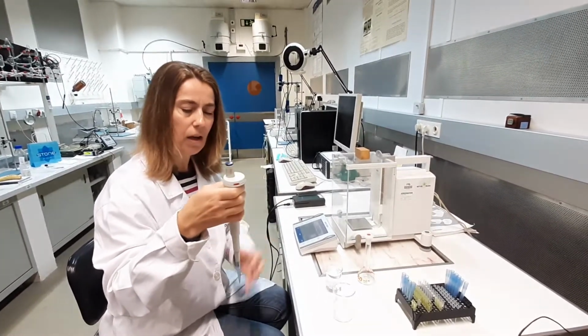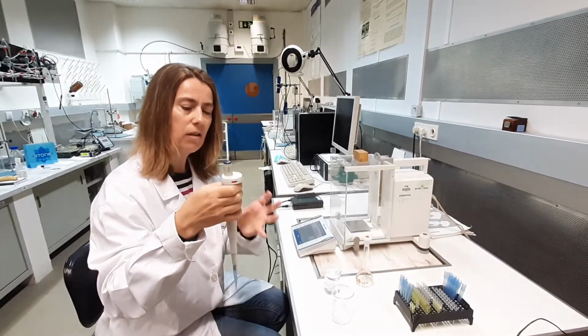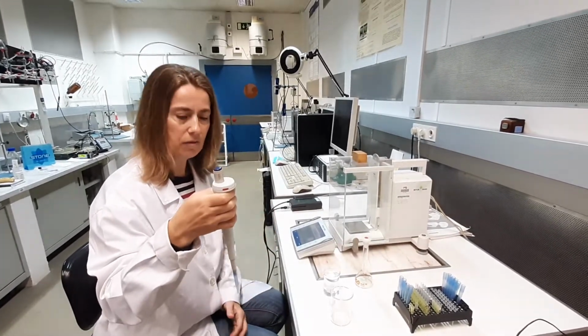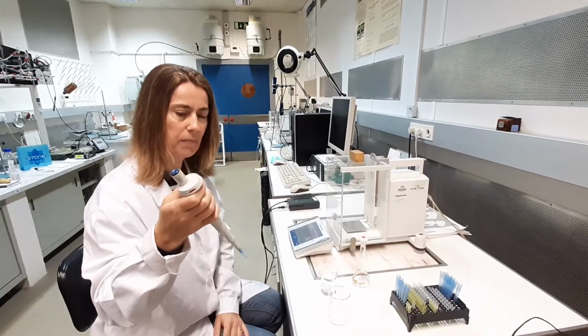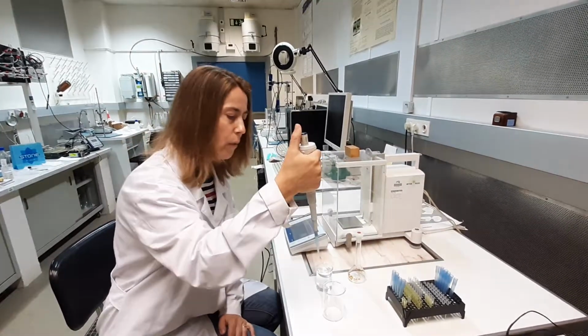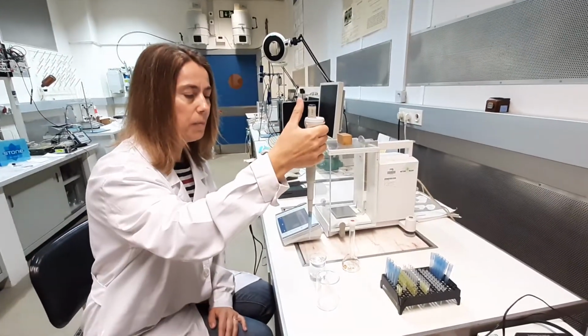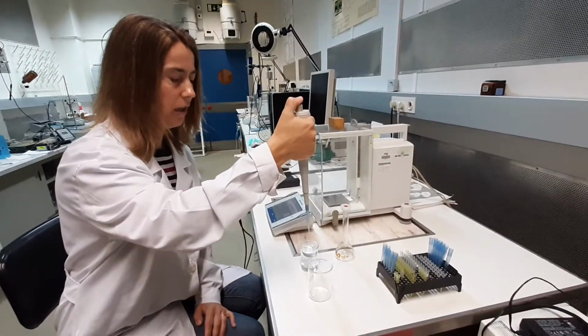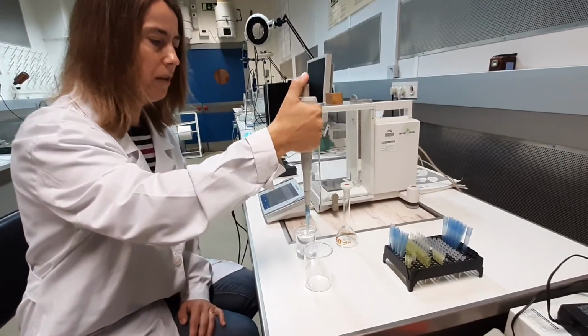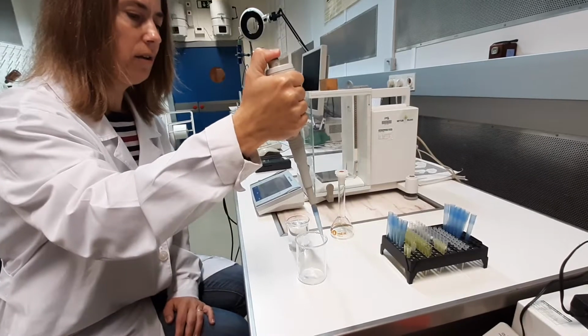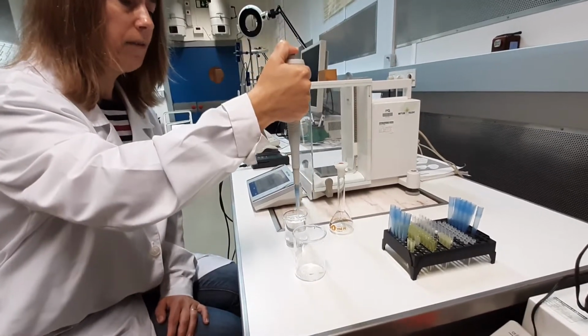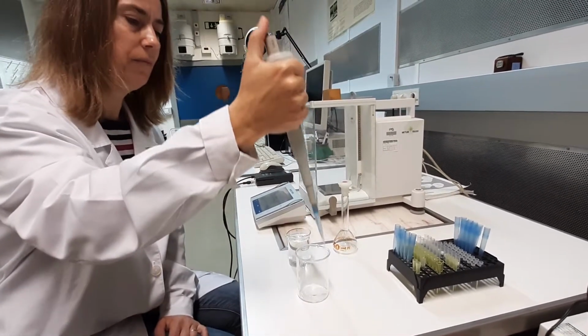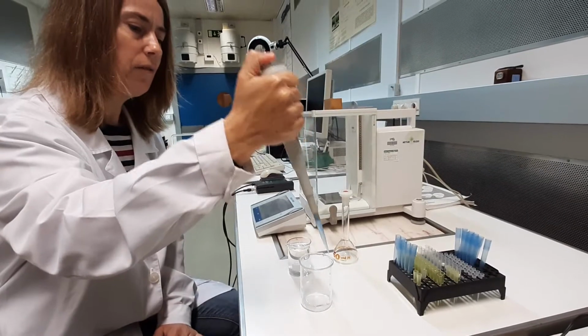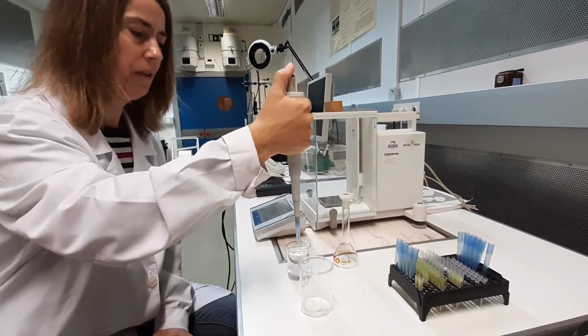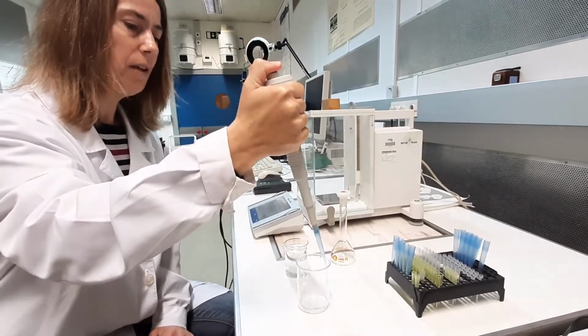Before we start the calibration, we need to fill the tip at least 5 times in order to have sufficient moisture inside of the tip and also of the piston. So we are going to fill the pipette with water 5 times. Always fill the pipette in a vertical position, and when we are delivering, always with an angle. So we do this filling 5 times.